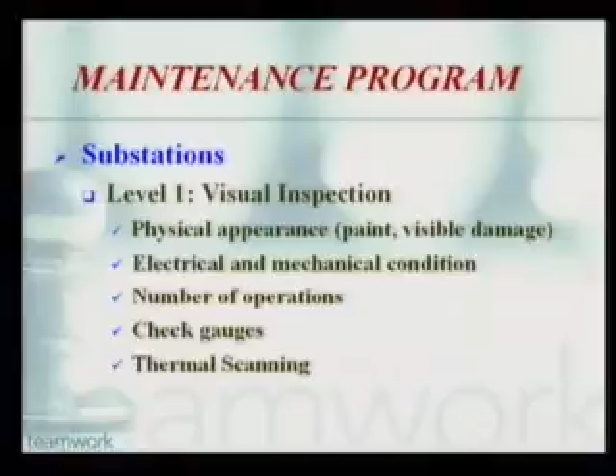And some of the programs that we have: level 1, which is a visual inspection, where basically once a month we go through and do a visual check. We check for mechanical condition, whether paints are cracking, if there are any leaks on the oil. Check the gauges. Transformer gauges basically record the hottest temperature that it's recorded. We want to make sure that none of that exceeds the standard that we follow for loading. And we also do thermal scanning, which is an infrared. I have several samples of what we do with the infrared scanning.